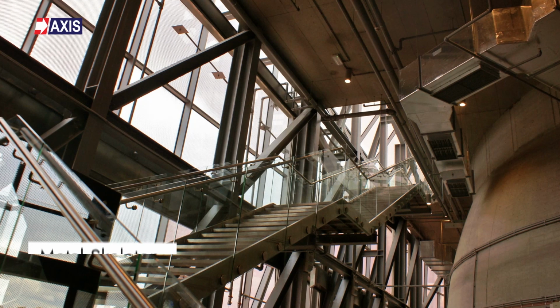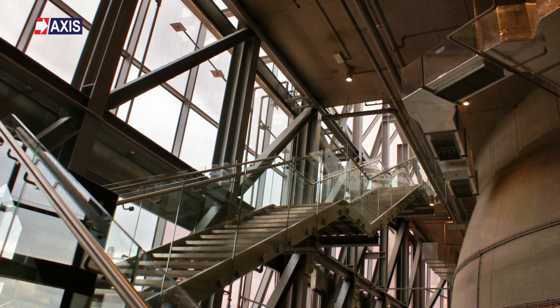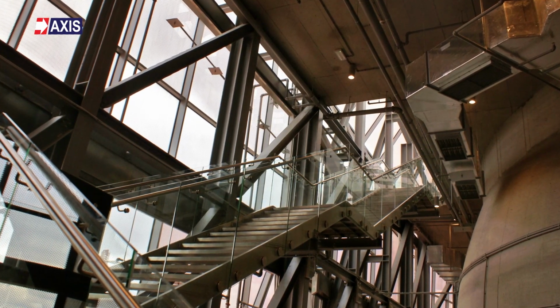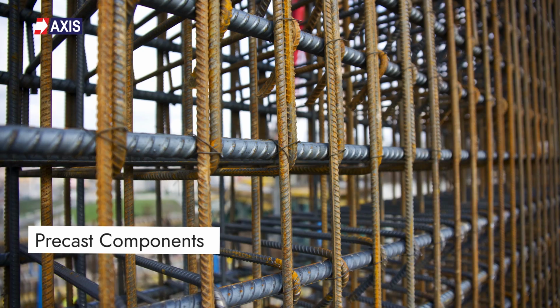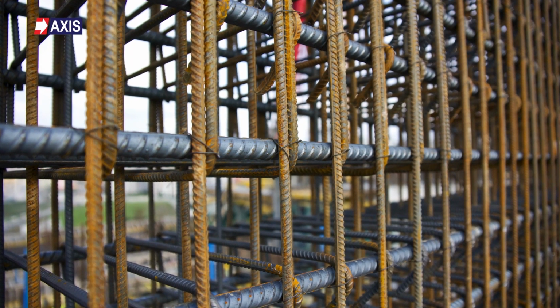Metal skeleton. If the structure of the building includes an interconnected metal frame, such as a steel skeleton or reinforced steel, this could serve as a down conductor system. In such cases, additional ring conductors might not be necessary, as the metal frame would already facilitate the splitting of the current. Precast components. In buildings that incorporate precast components, the terminal connectors for the reinforcement within these components can serve as natural down conductors, provided they maintain an electrically conductive connection.